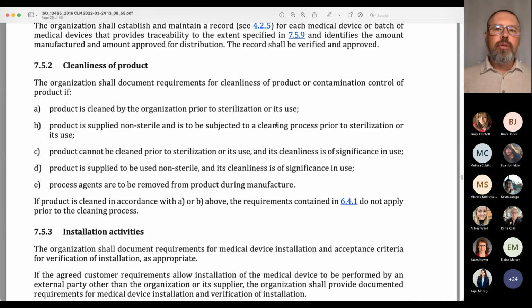Well, that baseline bioburden, that initial number, is very heavily influenced by the manufacturing environment and by the personnel performing the manufacturing. And if you have no clean room environment, or you have no way of controlling the environment that you're manufacturing in, then your baseline bioburden could have some pretty significant variability there. So this paragraph here is not necessarily a get out of jail free card that says, well, if you're going to wipe it down right before you send it to sterilization, then you don't have to have a clean room environment for your manufacturing process. It just means that there is some additional leniency where if you can establish some consistency outside of a clean room environment that gives you a repeatable baseline bioburden, then you might not need a fully certified clean room.